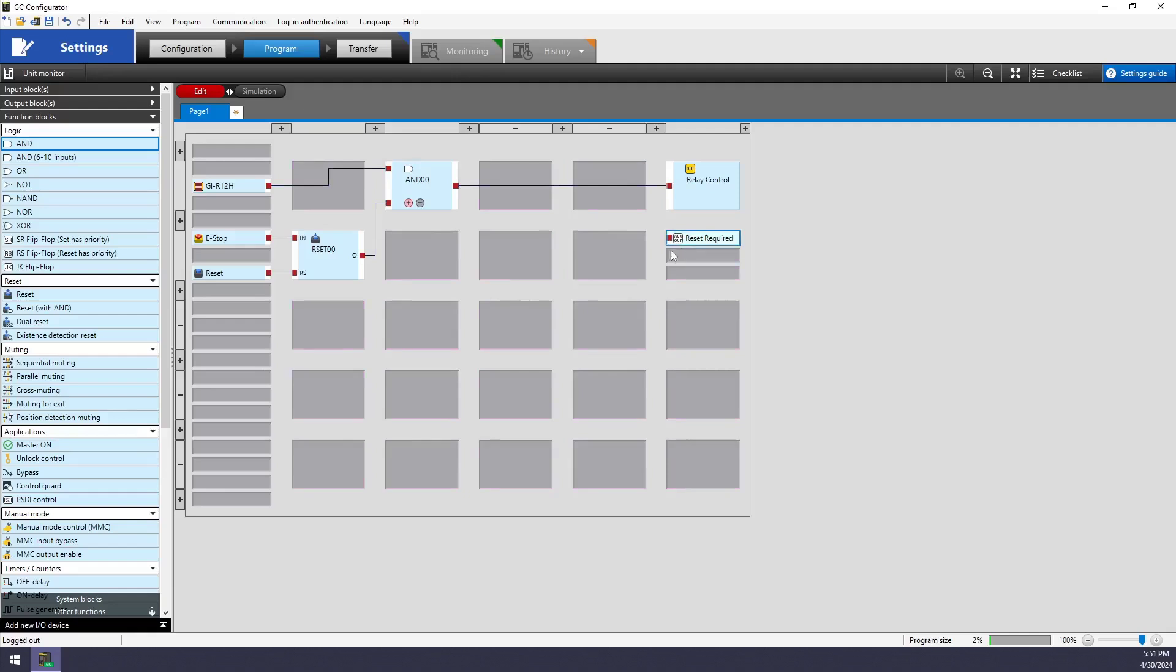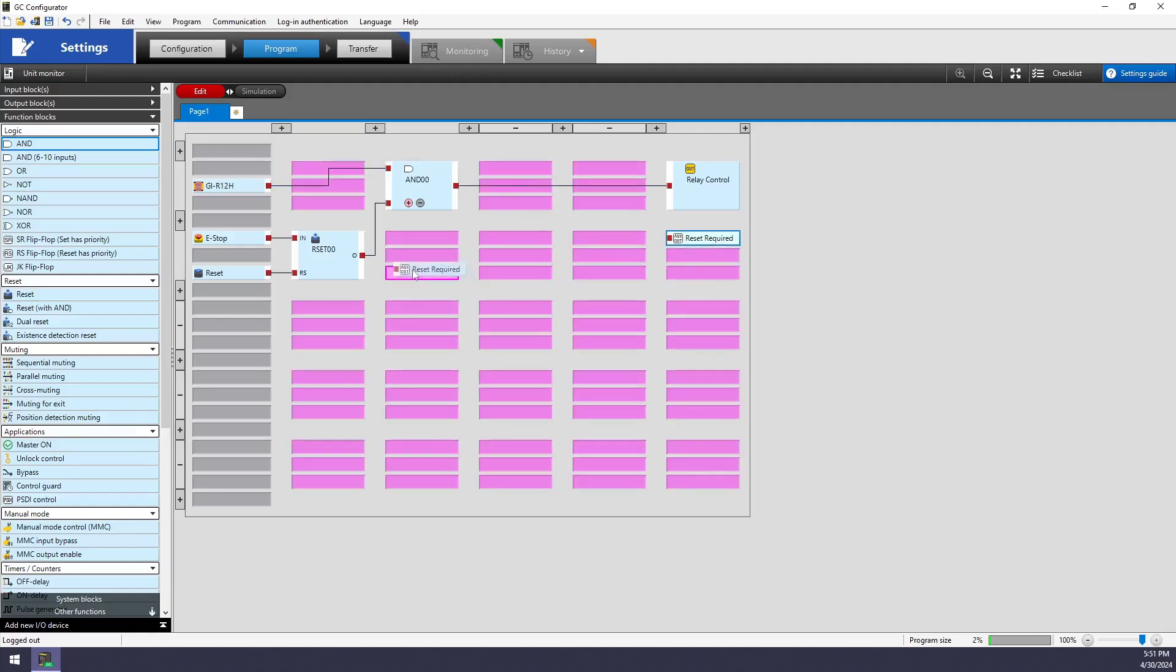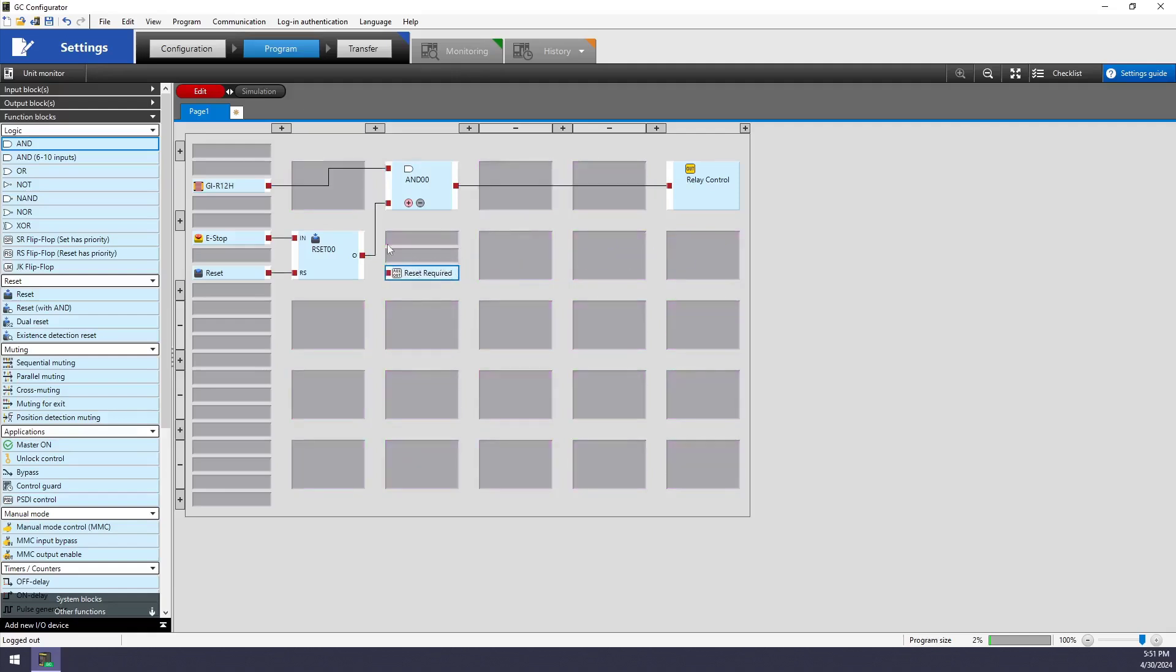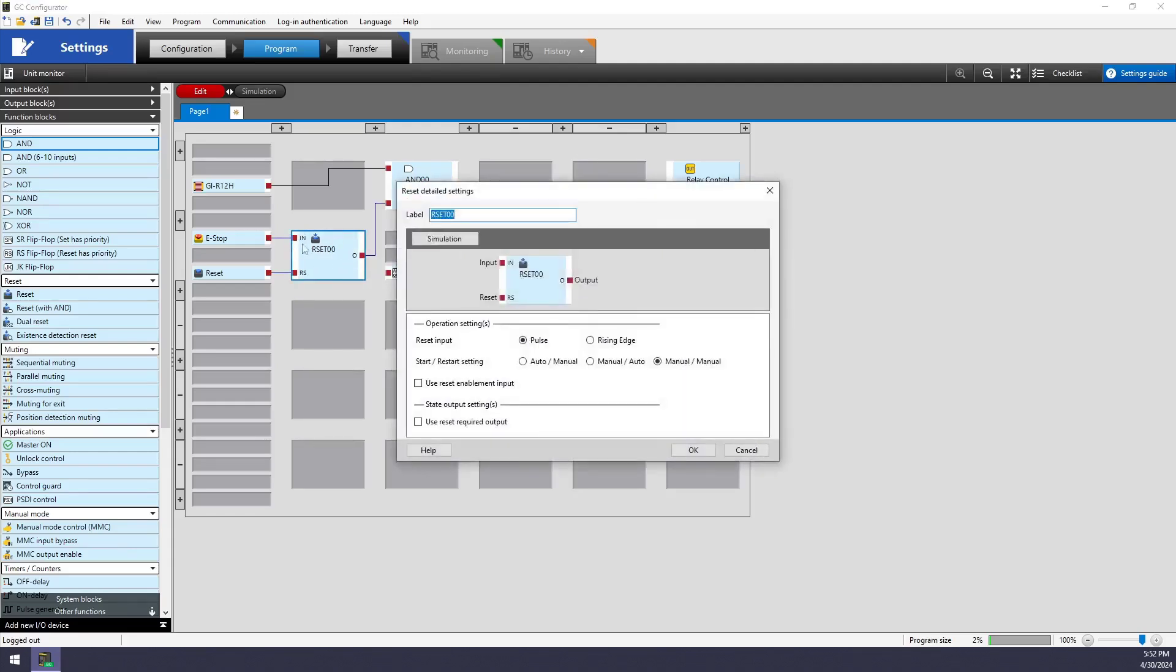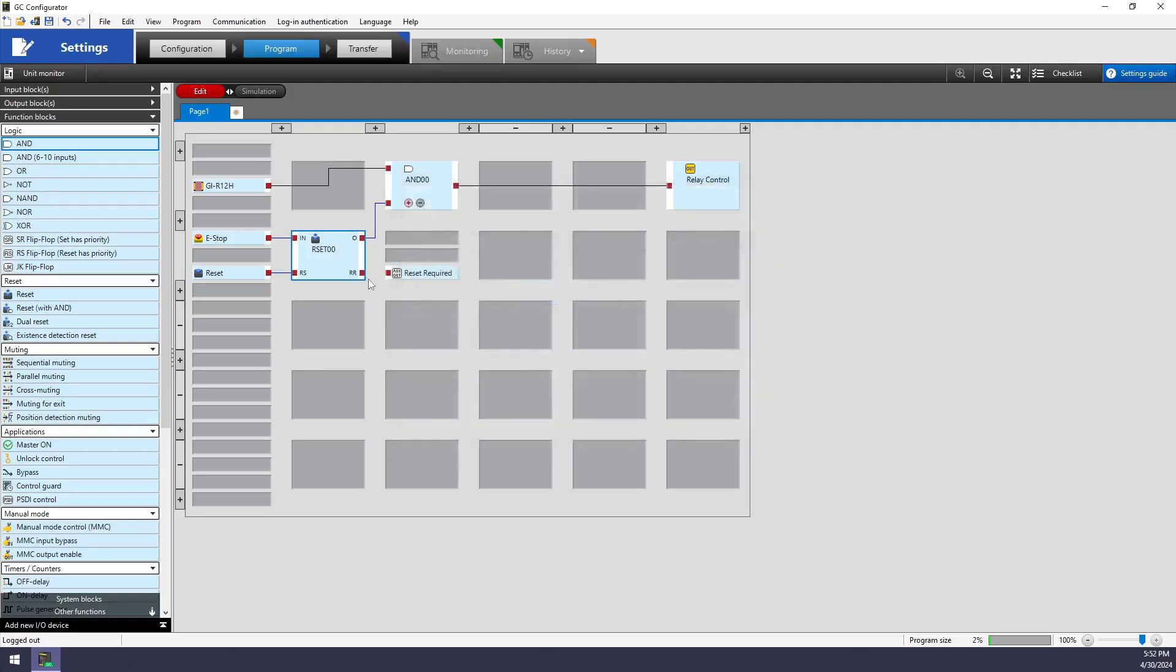Now what I've forgotten about here is my reset required status indicator. To add this functionality to the reset block, I can go into the detailed settings and say use reset required output. This is going to add a node that I can then tie to my output that will turn on whenever the reset function is waiting on that reset button to get pressed.